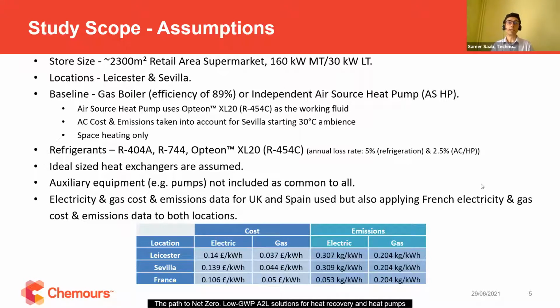The baseline solution would be a supermarket equipped with a gas boiler, having an efficiency somewhere around 89%, which is the average of gas boiler efficiencies, or an independent air source heat pump to perform the heating of the spaces. And we have only considered space heating in this application. So we did not consider any needs for sanitary hot water or other heating needs. We have used the Opteon XL20 as a working fluid when it comes to air source heat pump. And when we are looking at Sevilla results, we have included as well air conditioning cost and emissions because the ambient temperature requires to have air conditioning needs, especially when the ambient temperature is above 30 degrees C.